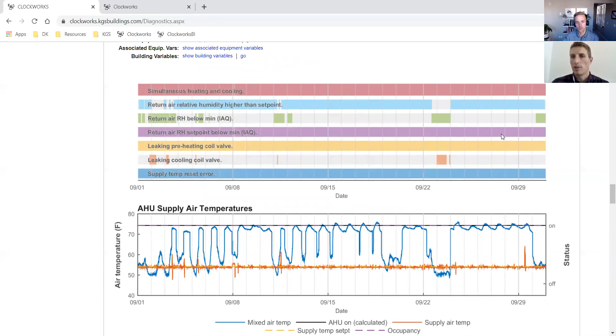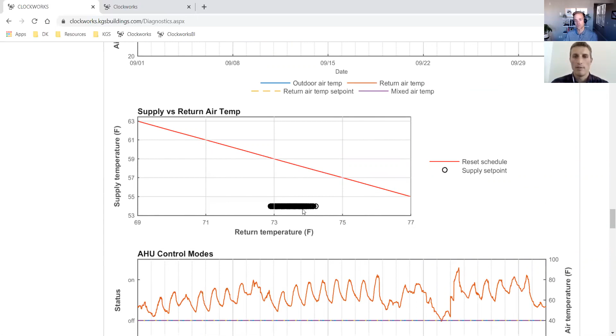So 5-minute interval data showing you temperatures, showing you when these issues occurred throughout the month period that we're analyzing, showing you that supply temperature reset. So here's why we recommended you implement that reset strategy, because right now your set point is locked in at 54 degrees.